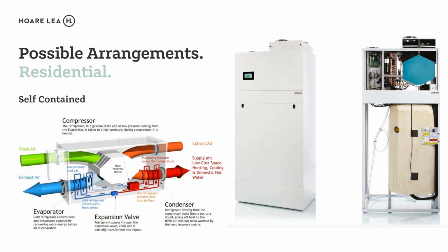But we are seeing that there's some benefit to this if you have a very low hot water demand and are prepared to wait a long time for heat generation, so hot water generation, and they are a viable solution, but there are limits on that. And then there's also the issue of hot water storage with heat pumps integral to it, which is on the right hand side there. A lot more compact, but they are looking at a packaged unit.